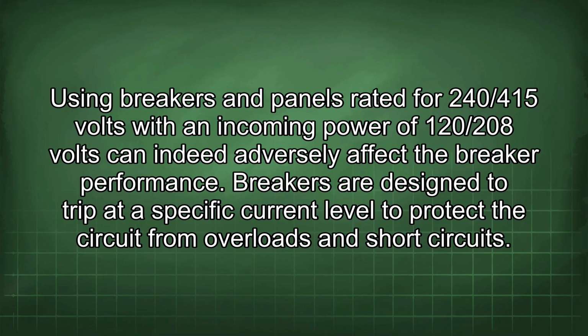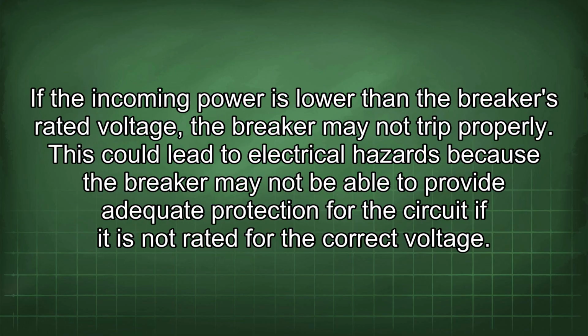Using breakers and panels rated for 240/415 volts with an incoming power of 120/208 volts can indeed adversely affect the breaker performance. Breakers are designed to trip at a specific current level to protect the circuit from overloads and short circuits. If the incoming power is lower than the breaker's rated voltage, the breaker may not trip properly.